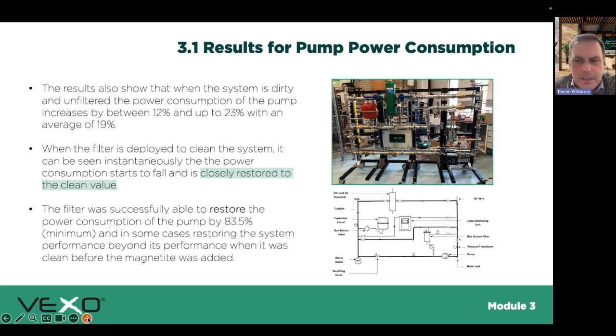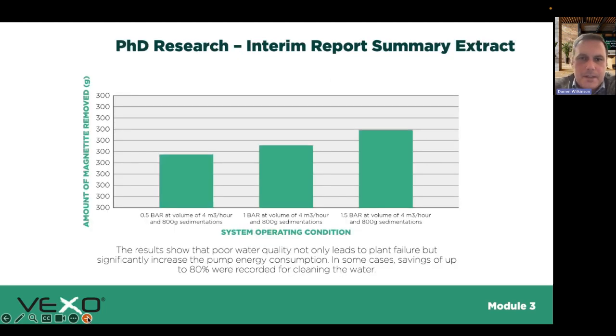So it's always been a difficult one - how much is this going to save me? Like all questions, it ultimately comes to what's the return of investment? You need to ask yourself if the water quality in that system is so poor that the pumps are working harder, you're having failures, and pipework is leaking. I think we can all associate that if we've got poor water quality, we're going to be heading in that direction. So that does have an impact in terms of the efficiency of the system.